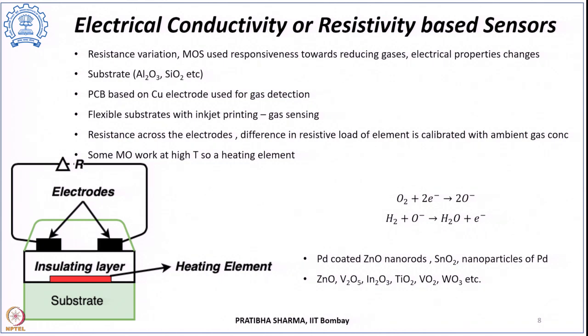Another class is the electrical conductivity or resistivity-based sensor. Changes in resistance or conductivity of the sensing element are mapped to hydrogen gas concentration. These typically use metal oxide semiconducting structures — a substrate of aluminium oxide or silicon dioxide with an insulating layer, a heating element for metal oxides that operate at higher temperatures, interdigitated electrodes, and a metal oxide layer on top.